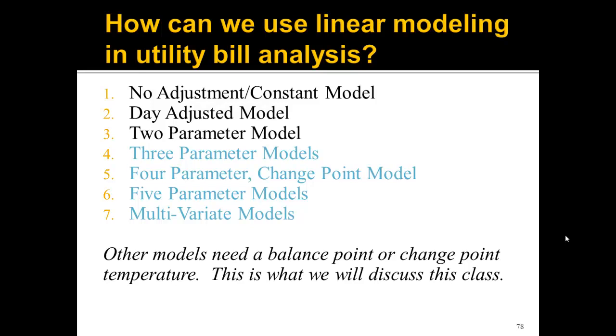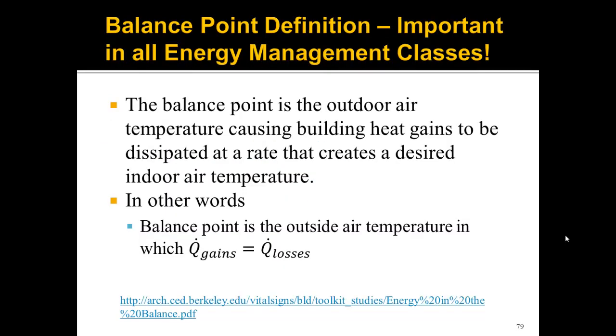This is what we're going to discuss this class. Let's look at the definition of balance point. This is not just important in this class, but in all energy management classes — it's a really important concept, so we're going to spend a good bit of time on it. The balance point is the outdoor air temperature causing building heat gains to be dissipated at a rate that creates a desired indoor air temperature.